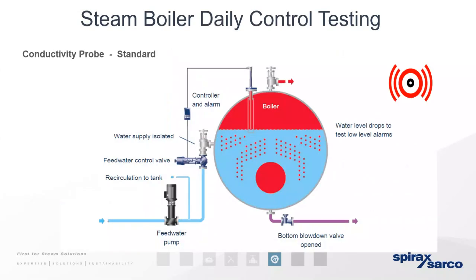And conductivity probes. This answers the question you were asking about the feed water in this particular case, where you're using conductivity. It should be a daily test to make sure it's working correctly, that it's turning the water supply on and off, or keeping a level, depending on whether it's modulating or on-off control. You do not need to test the high and the secondary low controllers on a daily basis. All you're doing is making sure that the probe changes the flow.